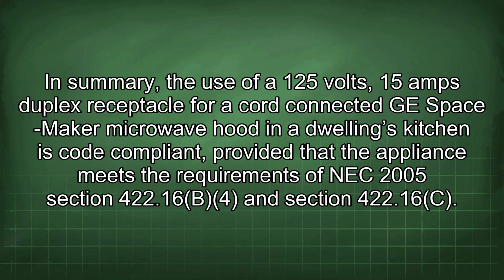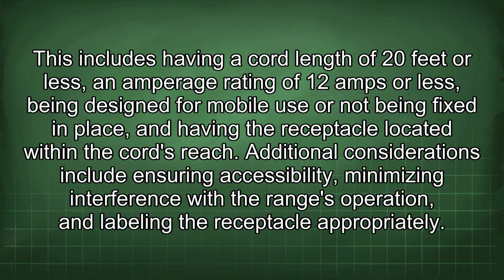a dwelling's kitchen is code-compliant, provided that the appliance meets the requirements of NEC 2005 Section 422.16(B)(4) and Section 422.16(C). This includes having a cord length of 20 feet or less, an amperage rating of 12 amps or less, being designed for mobile use or not being fixed in place, and having the receptacle located within the cord's reach. Additional considerations include ensuring accessibility, minimizing interference with the range's operation, and labeling the receptacle appropriately.